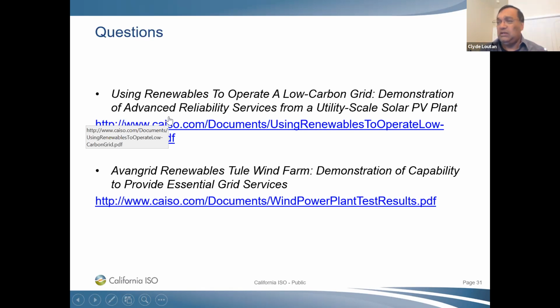Now, eventually, if we have newer standards or go beyond 2030, we do realize we could have an inertia problem, which means we cannot arrest system frequency. We operate at 60 hertz, but if you have a contingency and frequency drops to 59.5, that's when we start dropping load dramatically. We have frequency relays set to drop blocks of load starting at 59.5.